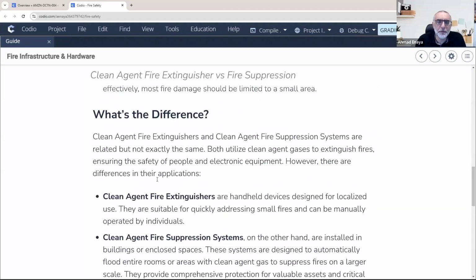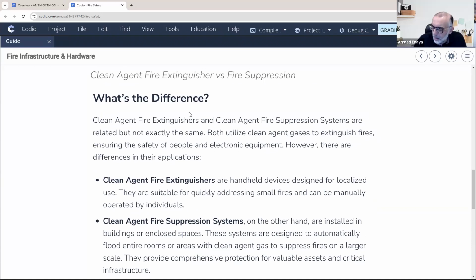Now, there are two types of fire suppression, let's say. There is the small scale, the fire extinguishers, which are the cylinders we have in every house, every kitchen. They are mainly handheld devices for local use only, not for a system or a center. They use a clean agent. We can also use clean agent in a suppression system—we can have it in a data center with a full system of detectors and sprinklers, and the sprinklers will spray clean agent instead of water. So these are the different ways for extinguishing.